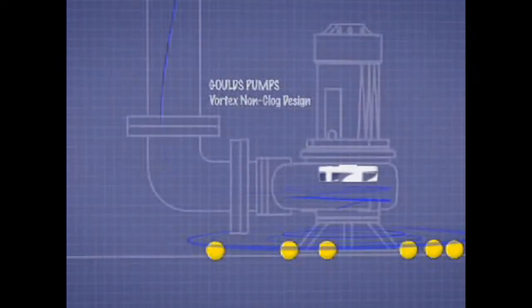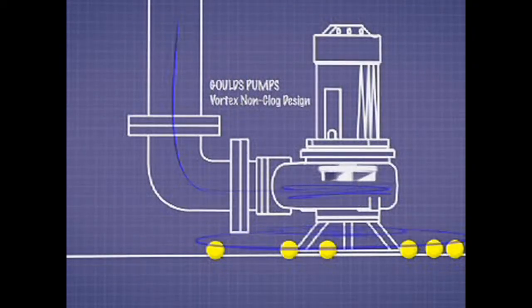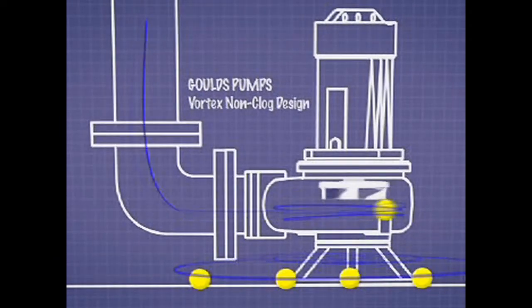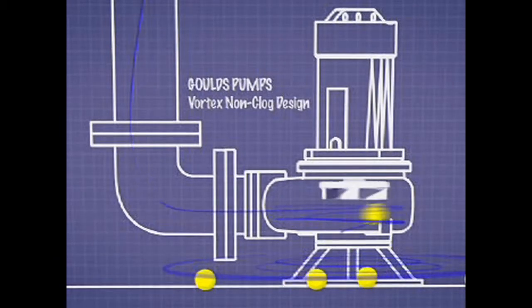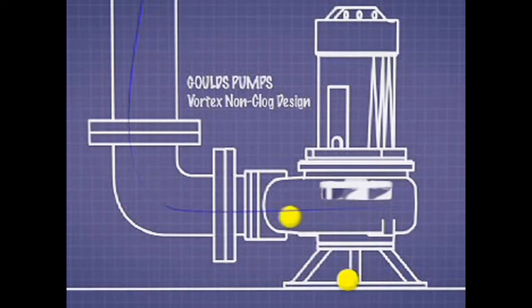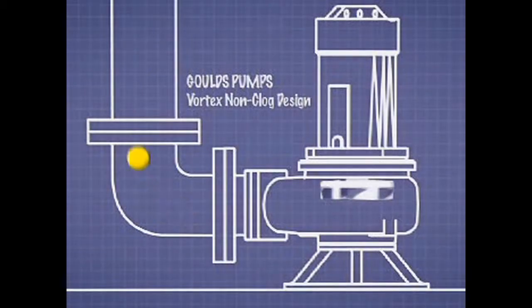What happens is it creates a cyclone and it carries the waste in the tornado, never having to come in contact with the impeller of the pump. I think one of the biggest advantages is the elimination of clogging. With the Vortex, that solid actually enters the casing and moves through the pump without ever entering the vanes at all.